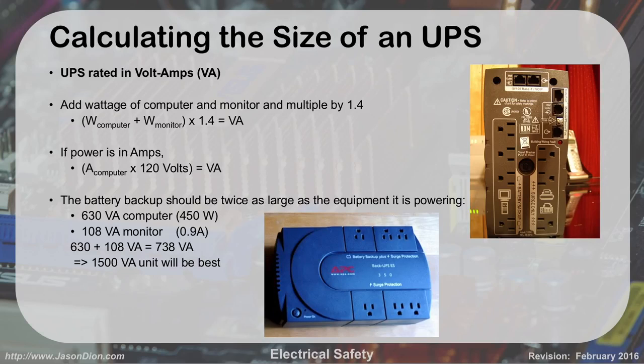So how do you calculate the size of a UPS? The UPS is calculated in what's called volt amps. You calculate that by adding the wattage of a computer and monitor and multiplying by 1.4. If your power is already provided in amps, you'd take the amps of the computer times 120 volts, which is what our power is in the US, and that gives us volt amps.